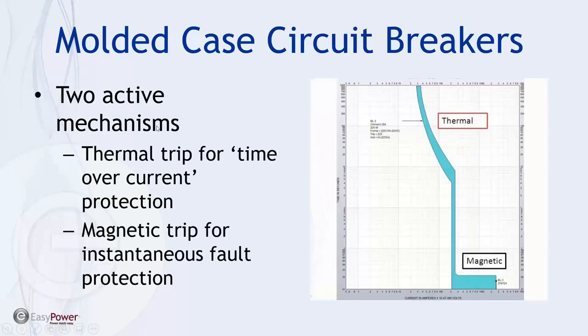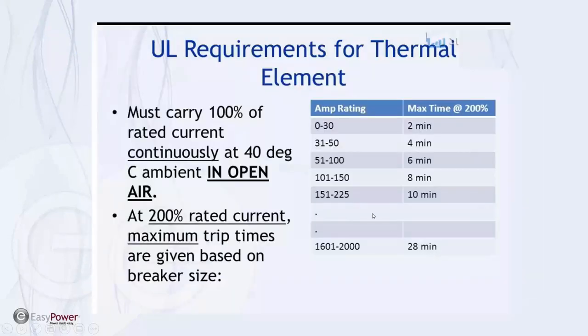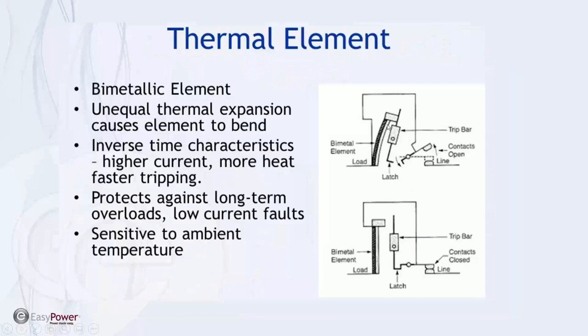In the case of molded case circuit breakers, we have two active mechanisms sensitive to overcurrent. First is a thermal element — a bimetallic strip that at a given current will bend enough to interrupt the connection. Then a magnetic trip, which acts as instantaneous fault protection. UL requires that the thermal element must carry 100% of rated current continuously at 40°C in open air, and 200% of the rated current at the trip times given for the breaker size.